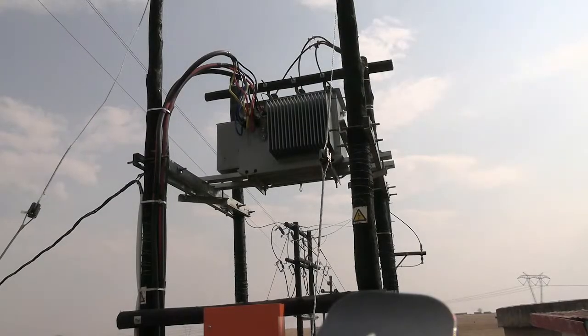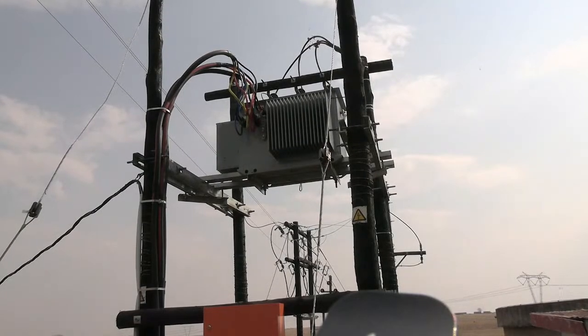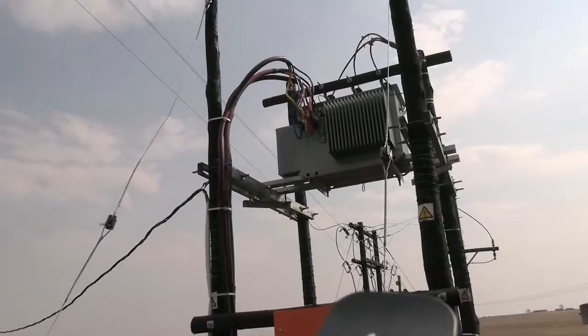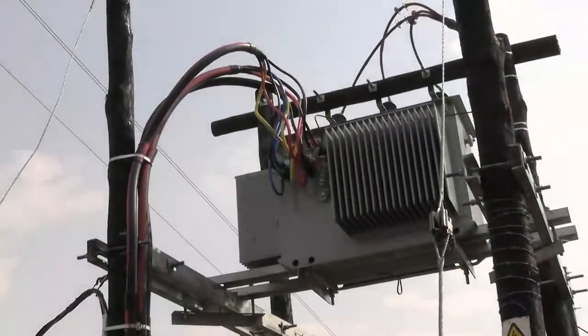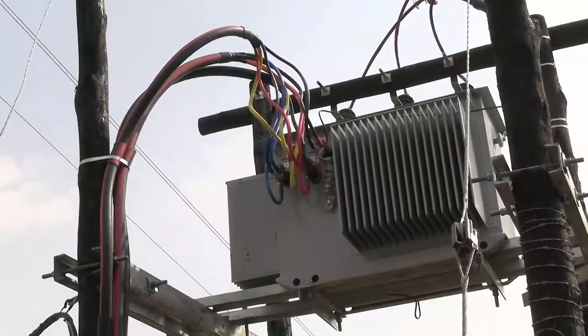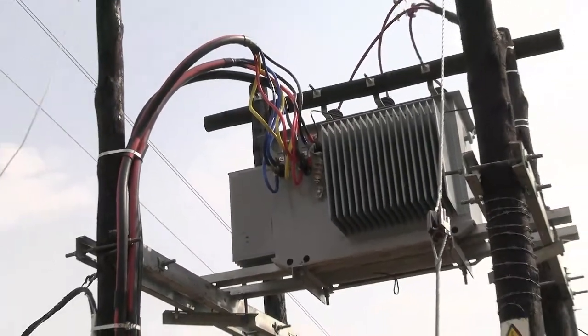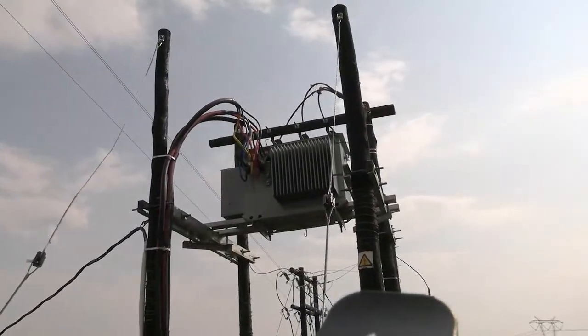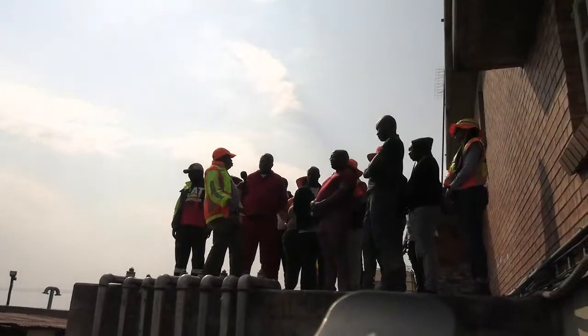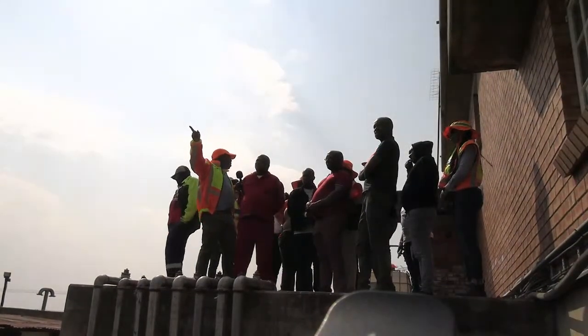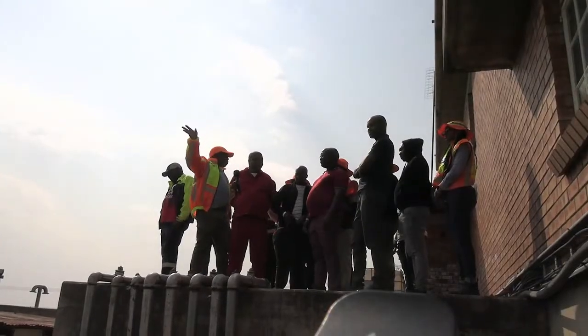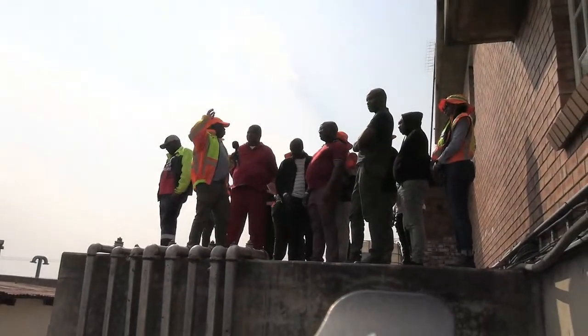So by saying that, I'm saying the municipality's transformer there can actually be utilized somewhere else. Right here, this is 500 kilowatt. You see we have 2 incomers and 1 outlet. Our scope of works was to electrify this thing, but since we have one transformer, we had to combine the demand here, the demand on the boreholes, hence 500 kVA.